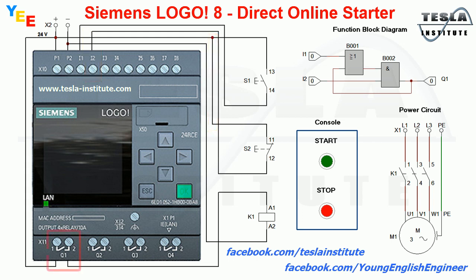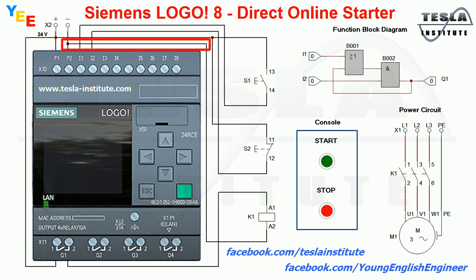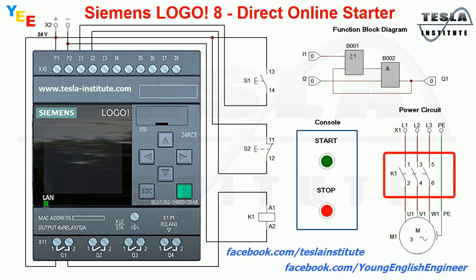To digital output Q1 is connected the coil of contactor K1. Terminal A2 of the coil is connected to the minus terminal of the 24 volt supply. In the power circuit we have motor M1, main contactor K1, and terminal block X1.